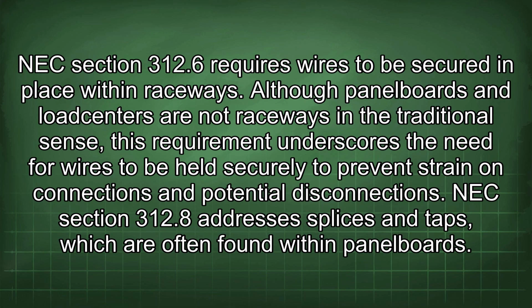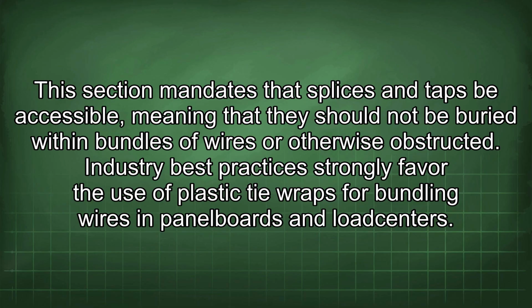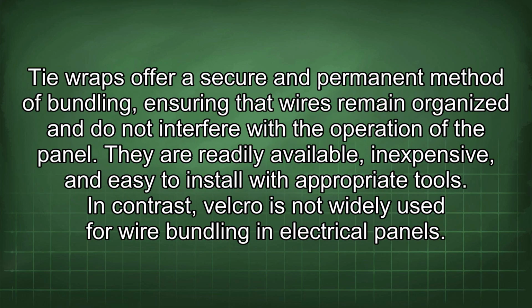NEC Section 312.8 addresses splices and taps, which are often found within panelboards. This section mandates that splices and taps be accessible, meaning that they should not be buried within bundles of wires or otherwise obstructed. Industry best practices strongly favor the use of plastic tie wraps for bundling wires in panelboards and load centers. Tie wraps offer a secure and permanent method of bundling, ensuring that wires remain organized and do not interfere with the operation of the panel. They are readily available, inexpensive, and easy to install with appropriate tools.